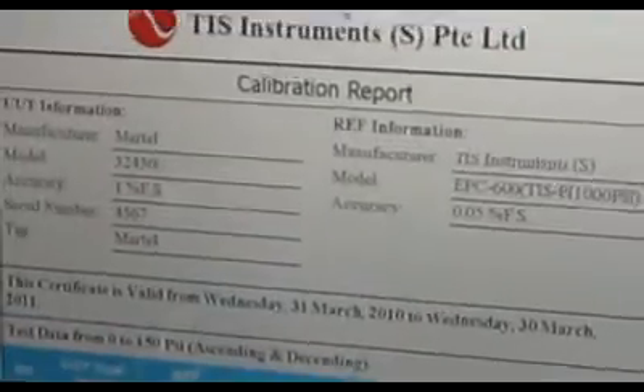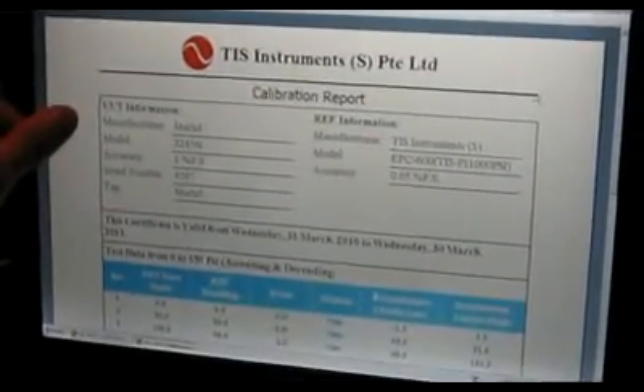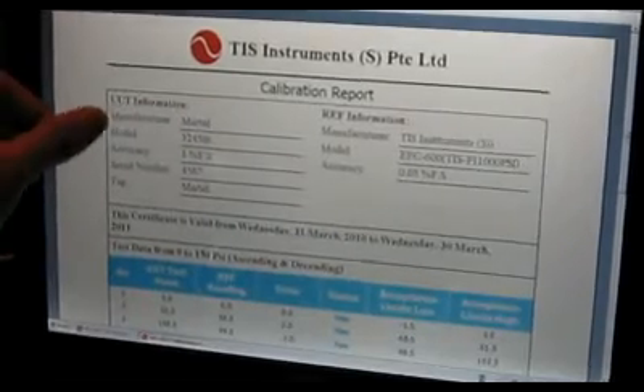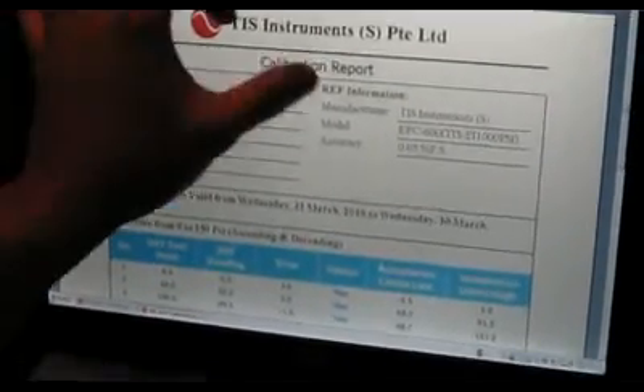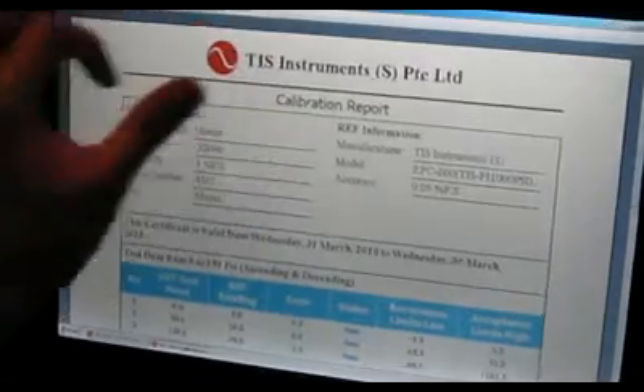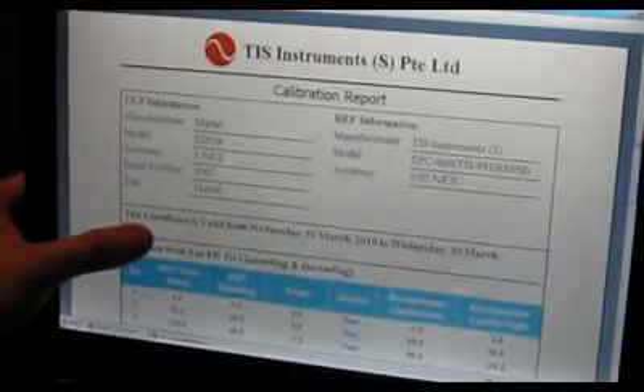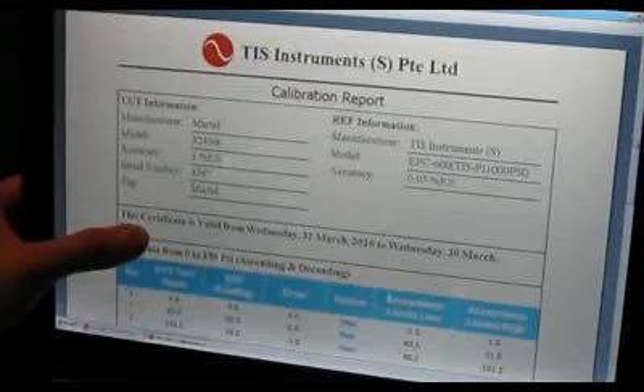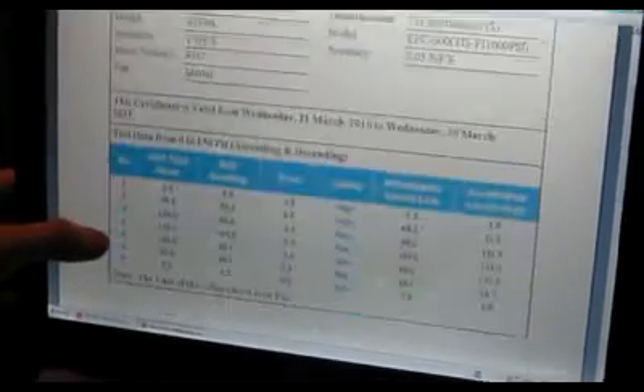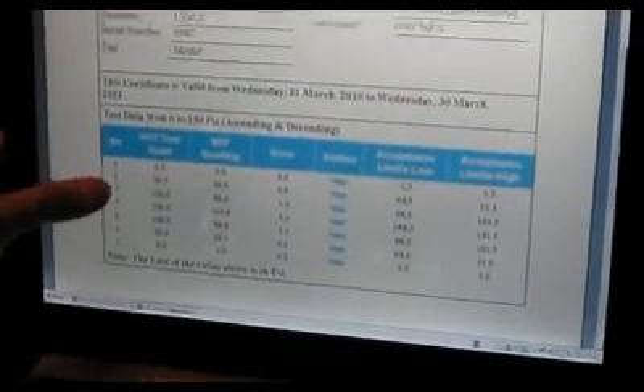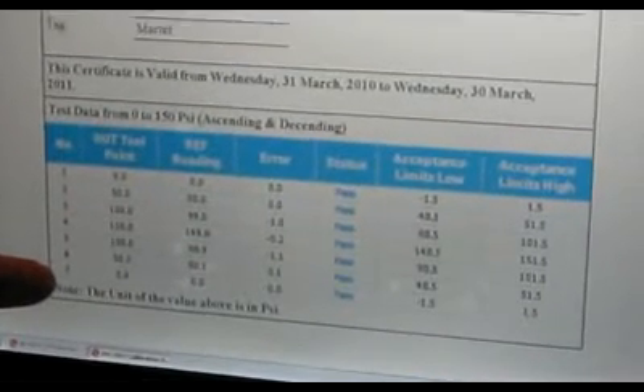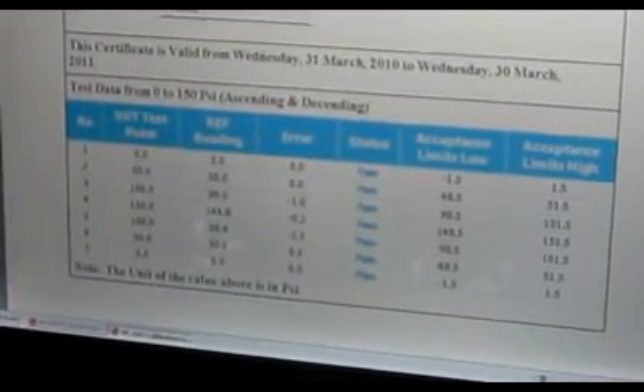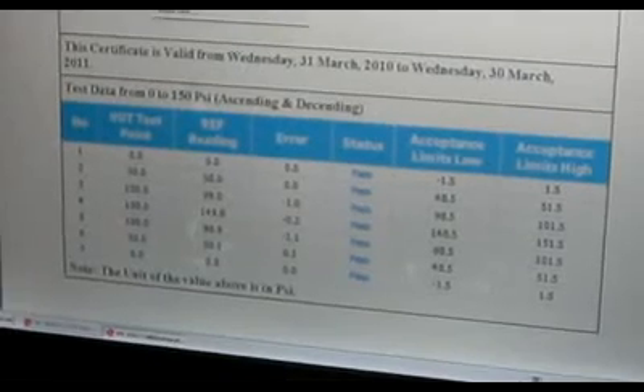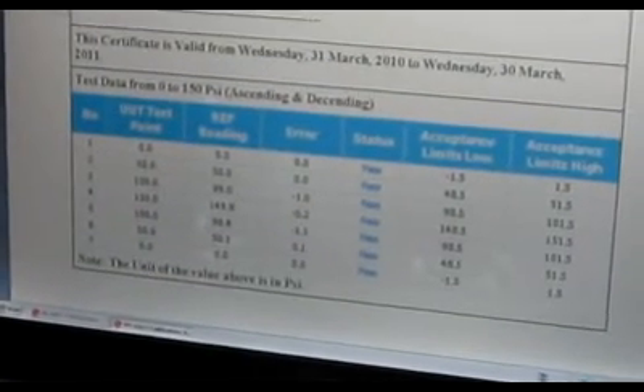The calibration report is presented with the UUT information, the reference, which is our master EPC600, the validity date of the calibration cert, which uses the system clock, and the test data with the number of points that we have just calibrated. We are able to export this document in Excel or PDF as per the customer reference. Let's export to Excel and save it to a location.